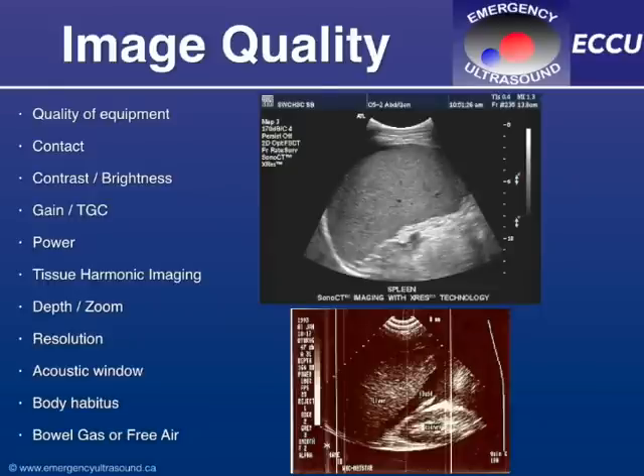Tissue harmonic imaging can greatly change the image obtained. This is the ability of the machine to listen for harmonics or multiples of the frequency. Depth or zoom, this is again important. Too much depth means that features that are close to the probe can be too small to see detail, and yet too little depth can of course mean that we miss deeper pathology. So again, it's important to start deep but remove the depth as you scan, so that the point of interest fills the screen.